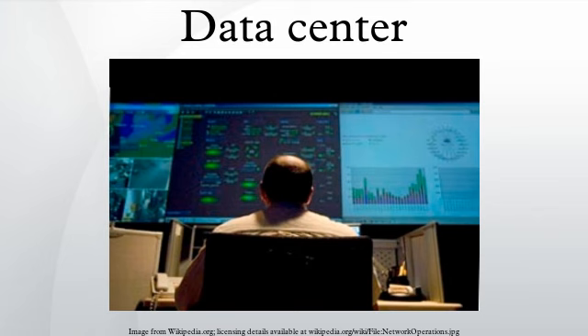Availability expectations: the higher the availability needs of a data center, the higher the capital and operational costs of building and managing it. Business needs should dictate the level of availability required and should be evaluated based on characterization of the criticality of IT systems, and estimated cost analyses from modeled scenarios. In other words, how can an appropriate level of availability best be met by design criteria to avoid financial and operational risks as a result of downtime? If the estimated cost of downtime within a specified time unit exceeds the amortized capital costs and operational expenses, a higher level of availability should be factored into the data center design. If the cost of avoiding downtime greatly exceeds the cost of downtime itself, a lower level of availability should be factored into the design.